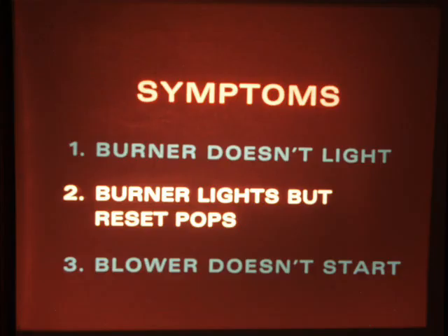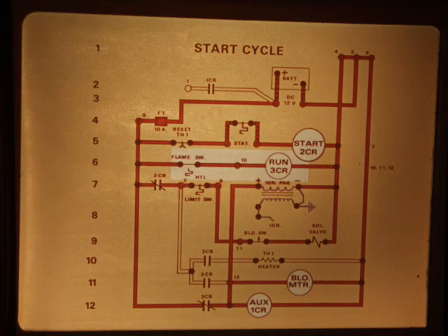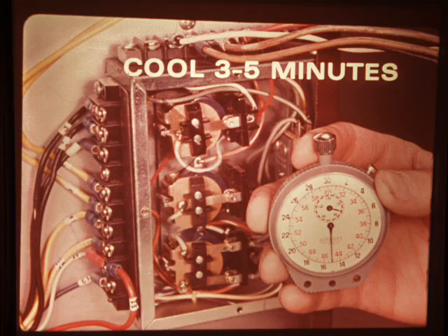Next, let's take the situation where the furnace fires, but the reset pops in less than 1 minute. Remember that the flame rod circuit should energize the run relay within 10 to 15 seconds after the furnace fires, and energizing the run relay bypasses the thermal reset heater, so it can't shut down the furnace. Trouble diagnosis, therefore, is aimed at determining whether the problem is the control box or the flame rod circuit.